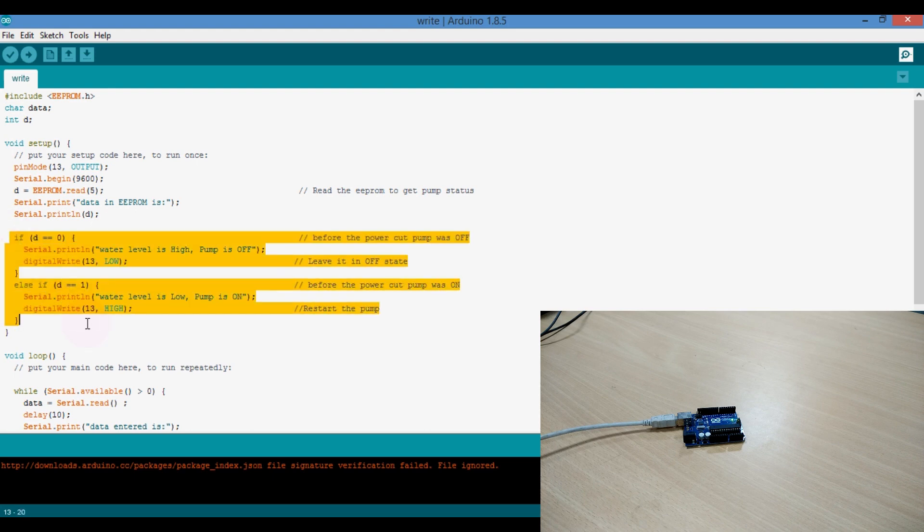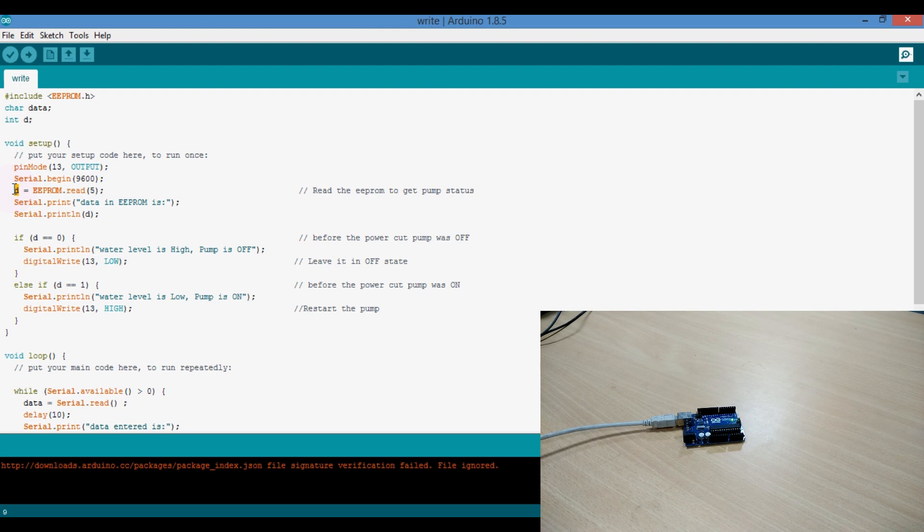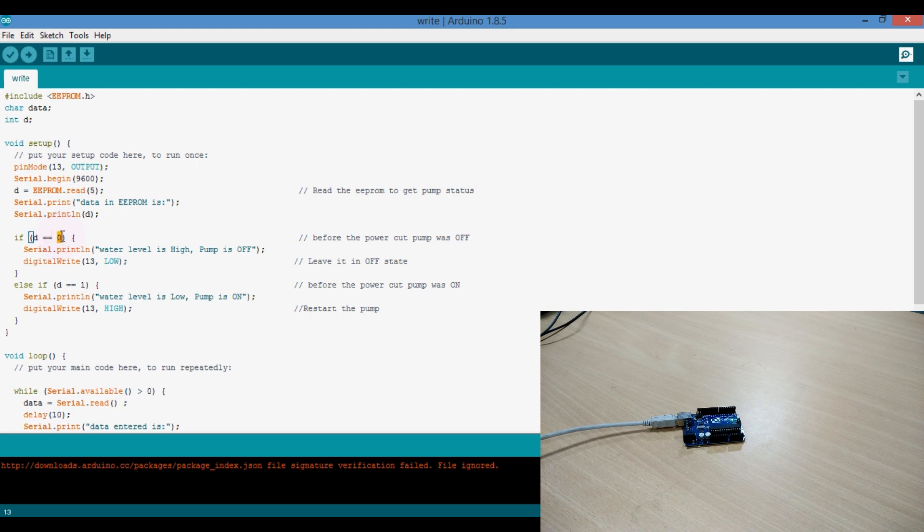So when the power comes again, the controller restarts and it executes the program from the start. Now in the setup, the program reads the location 5 and stores the data in the variable D. And this data is compared to zero, which means the status of the pump before the power was off.